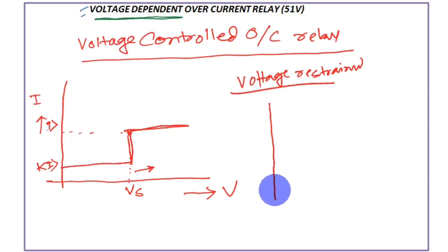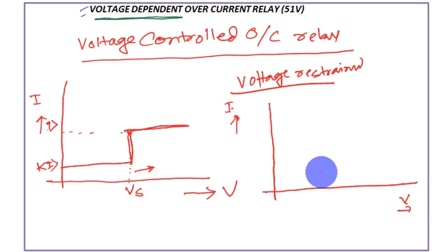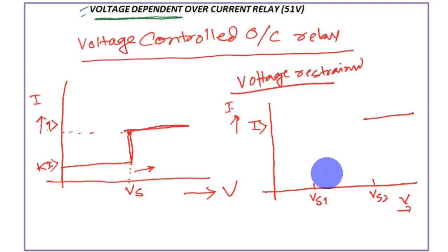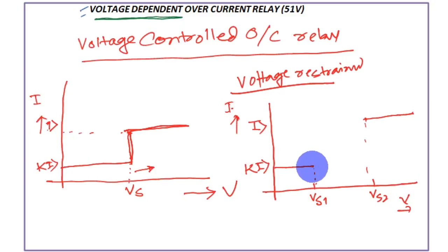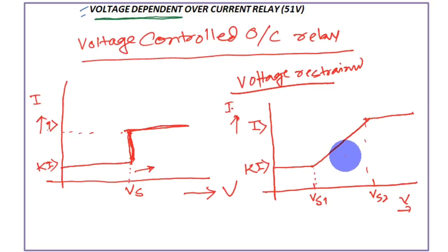In the voltage restrained overcurrent relay, there are two voltage set points: Vs1 and Vs2. Above Vs2, the pickup current is I_greater_than; below Vs1, the pickup current is Ki_greater_than. Between Vs1 and Vs2 there is a sloped transition — not an instantaneous step — which gives an IDMT-like characteristic. The more the voltage has fallen, the lower the pickup current, and the earlier the relay will pick up.